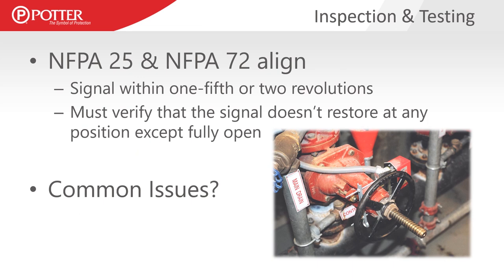NFPA 25 and 72 align in terms of what constitutes a pass-fail for a supervisory switch test. It's a signal sent within one fifth of a turn or two revolutions of the wheel. It must verify that the signal doesn't restore at any position except fully open — meaning you must run the stem all the way in and out to make sure that trip stem doesn't fall into the threaded grooves and restore itself at any position other than fully open. Common issues are often misalignment or misapplication — they don't get installed properly or get bumped and banged.